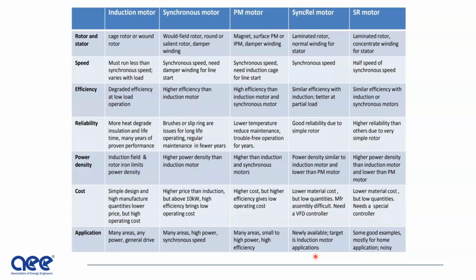Here you see the major classes of motors: the induction motor, the synchronous motor, the permanent magnet motor, which are very expensive, and the reluctance motors, which are very specialized motors, using an inverter to run the motor, which is part of the design drive for the motor. And you can see that in terms of the rotor and stator, the speed, the efficiency, the reliability, power density, I won't get into all these details. You can read it for yourself, but let your eyes gravitate towards the kind of motors you're using, and you can see the comparison between those motors and other similar motors.